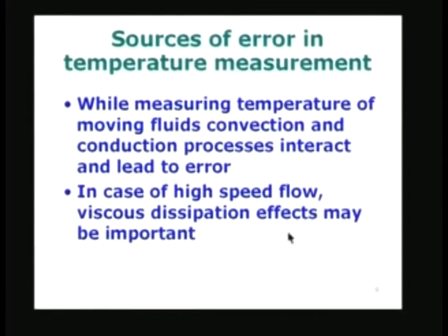But in normal practice, for example, air conditioned ducts carrying conditioned air, or a hot water application where you have hot water flowing through a tube, in a heat exchanger application for example, these viscous effects are not important, and we may be only involved in accounting for convection and conduction errors, and to some extent maybe radiation errors in some extreme cases.